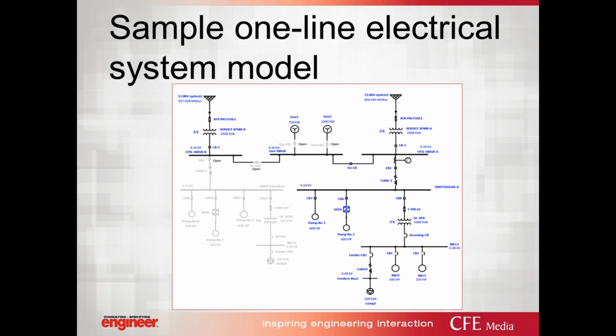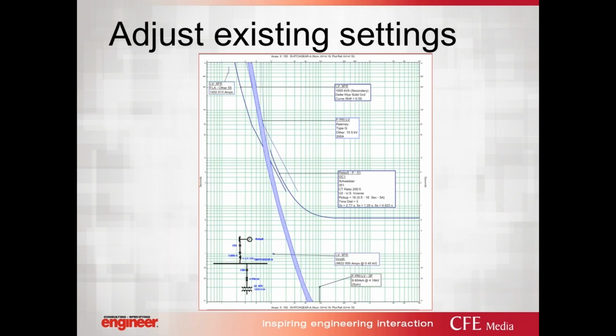There are 2 paths on utility injecting to this facility with 2 backup gen. Right now, I'm trying to emphasize on protecting the transformer, 1000 kVA transformer, by the fuse. Therefore, let's see how easily we can, using advantage of the set point, to reduce the incident energy. Therefore, if you look at in this TCC, I'm looking into the fuse protecting the transformer.